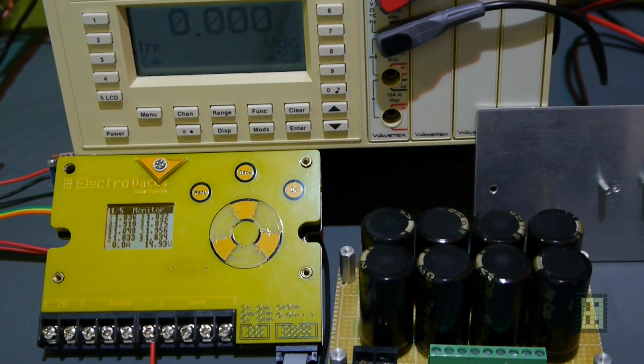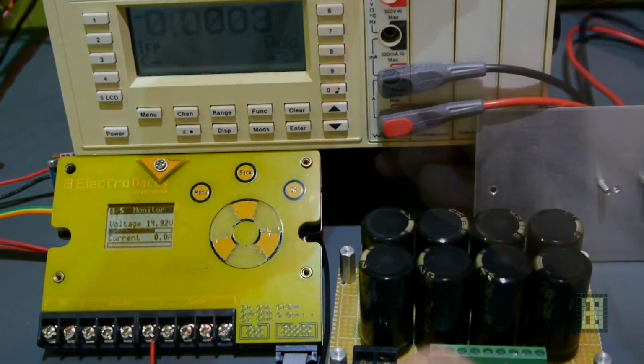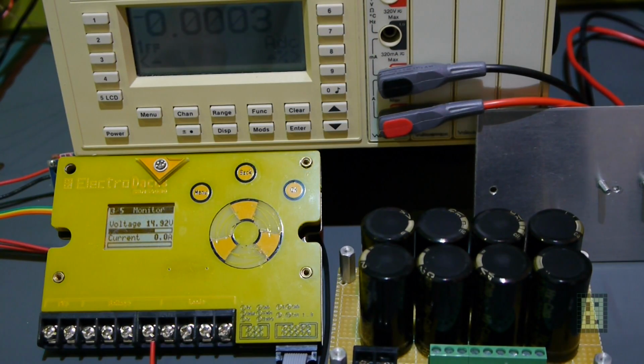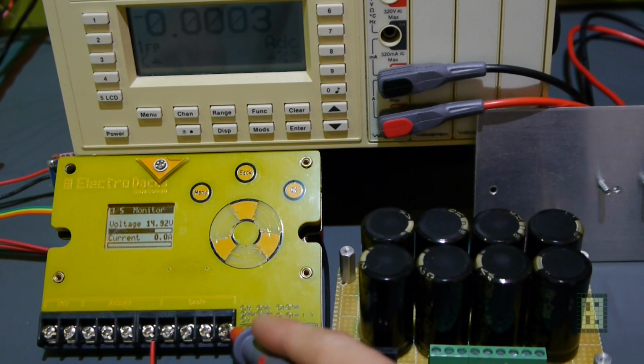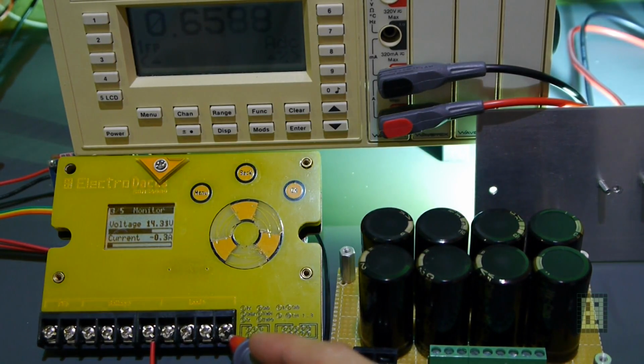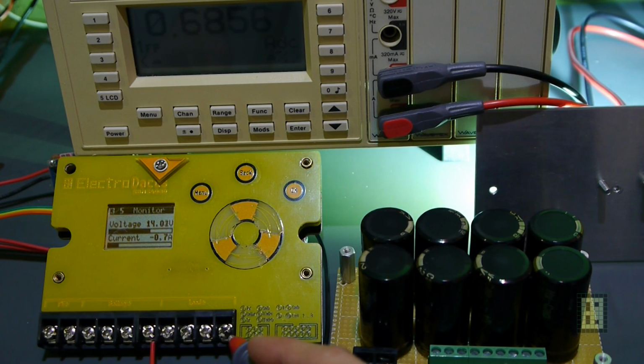And now I should measure the current. Let's measure the discharging current first: it's 0.68, 0.7 on the BMS. That's accurate enough - I don't have better resolution, and I cannot get better resolution for the BMS than 100 milliamps, but that should be good enough.